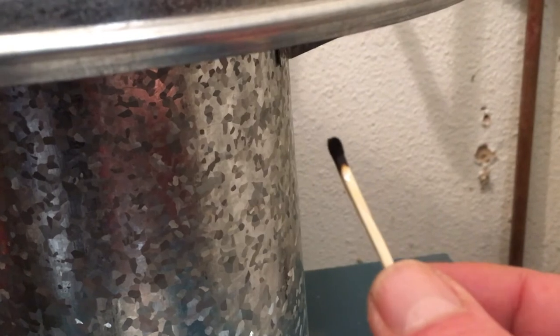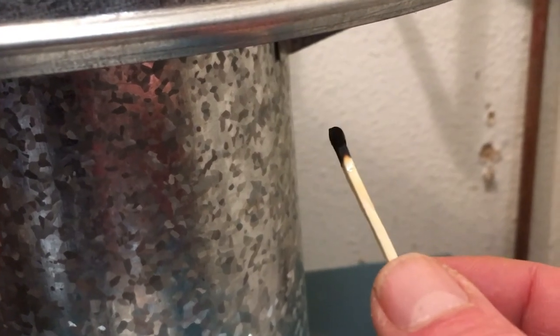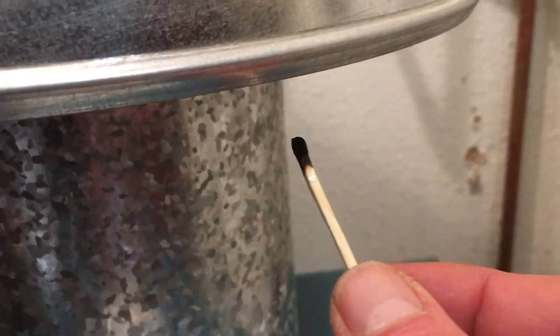Blow out the match or give it a shake so that it goes out, and watch to see that the smoke from the match flame is drawn up into the draft diverter, into the vent connector, and into the main chimney. You can see that there's a negative draw, a negative pressure in the venting system, which is ideal.